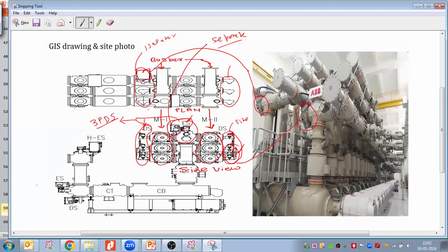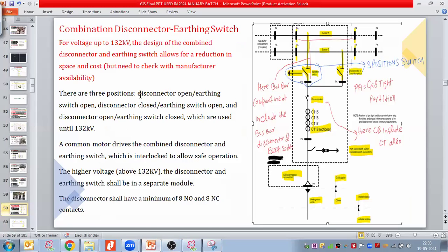And what are the 3 positions? Position 1: disconnector open, earthing switch open. In this position, my disconnector is open and the earthing switch is open, no operations, each in open position. Then the disconnector closes, so when I close the disconnector, the earthing switch stays open. Then the disconnector is open and the earthing switch closes, so the moving contact can close with this position. It means now the disconnector is open but the earthing switch is closed.